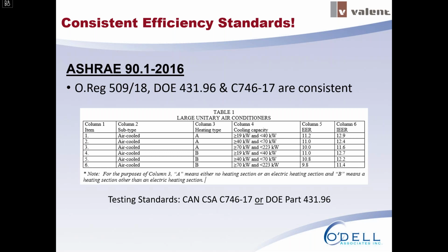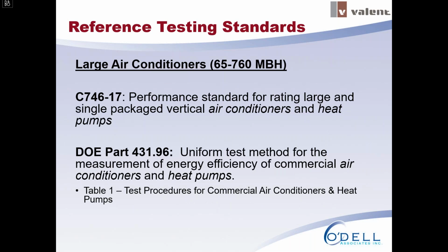So in summary of the testing standards, the reference testing standards for Ontario for large air conditioners from 65 to 760 MBH are C746-17 and DOE Part 431.96. They differ a bit in that standard C746 goes into quite detail on the test procedures needed for calculating the efficiency. It goes right into what temperatures and what position to set your return air damper at, and outside air conditions. DOE is a little different in that they reference a table that tells you what AHRI standard you are to reference depending on what style of product you're testing.